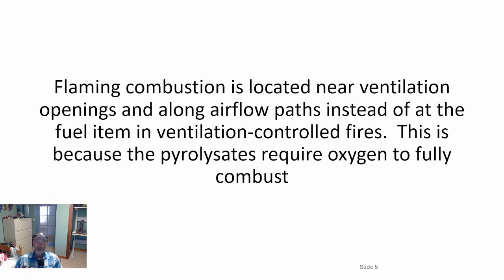This is because of the products of pyrolysis — let's define that. When you heat up cellulose or wood-based material, there's off-gassing. Solids don't burn; the gases burn. During pyrolysis, you reach a certain temperature causing molecular breakdown and off-gassing of gases that, if exposed to oxygen, can be ignited through piloted ignition.